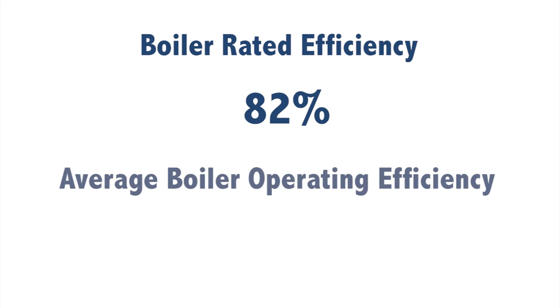If you take a fluidized bed combustion boiler, the efficiency promised by the boiler manufacturer is 82% with the air preheater and the water preheater included. But when you really run the boiler, typical average efficiency for these boilers is 63%. So why is the gap? On one hand, there is a promise of 82% while the operating efficiency is 63%. So what is the reason for this gap?